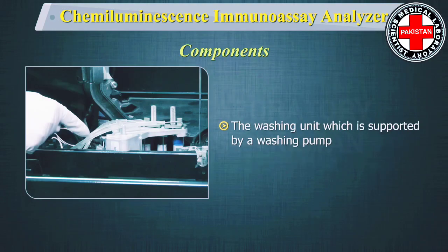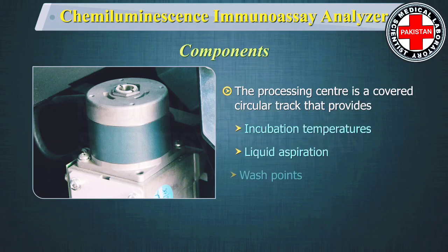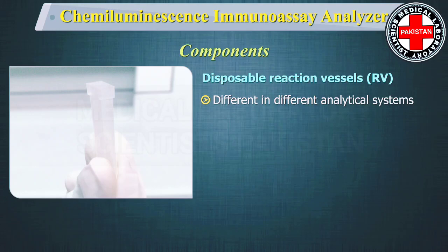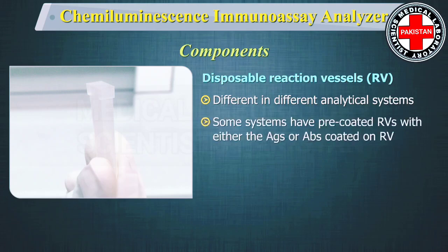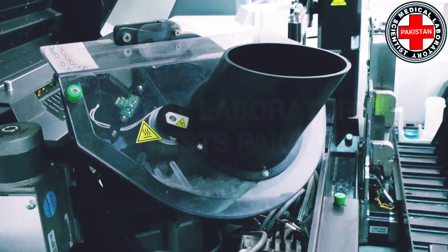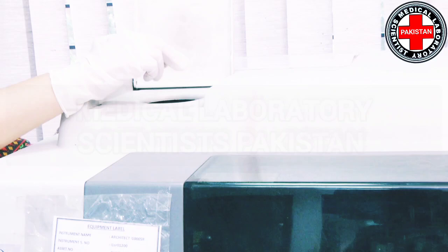The washing unit is supported by a washing pump. The processing center is a covered circular track that provides incubation temperatures, liquid aspiration, and wash points as necessary for the assay protocol. Disposable reaction vessels differ across analytical systems. Some systems have pre-coated reaction vessels with either antigens or antibodies. If an antigen is to be detected in a sample, then the corresponding antibody will be coated and vice versa. The reaction vessel is dropped into the reaction vessel loader and hopper assembly, which provides on-board storage and transports vessels into the process path.